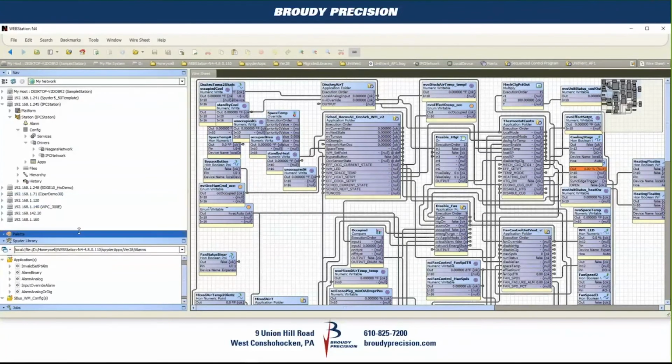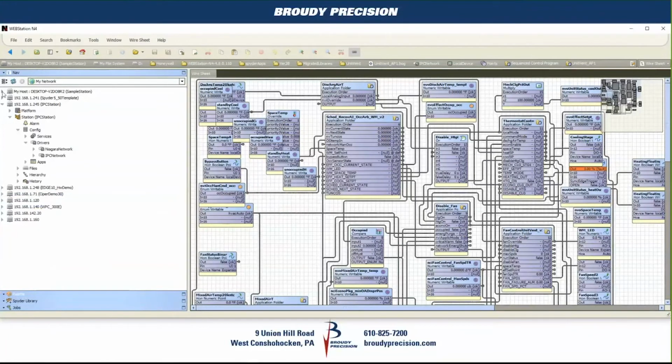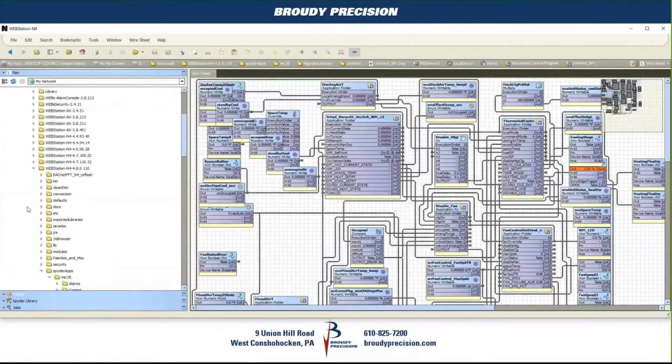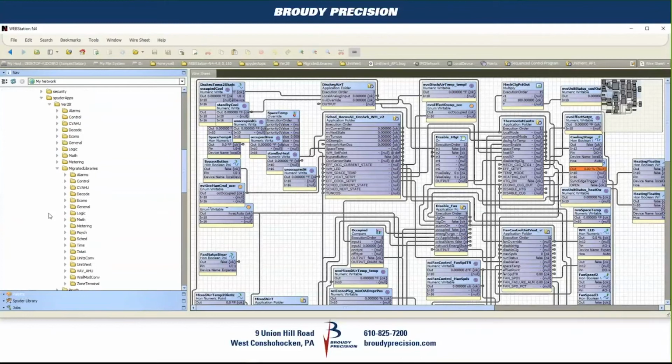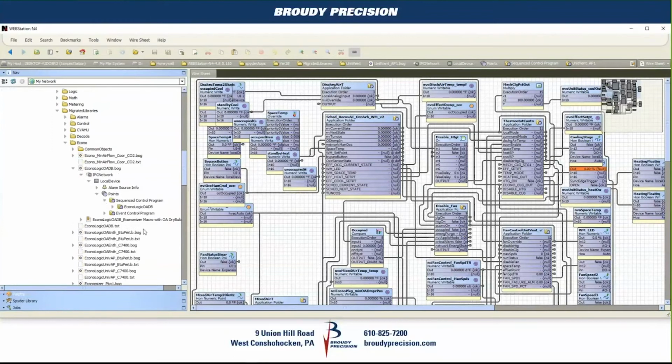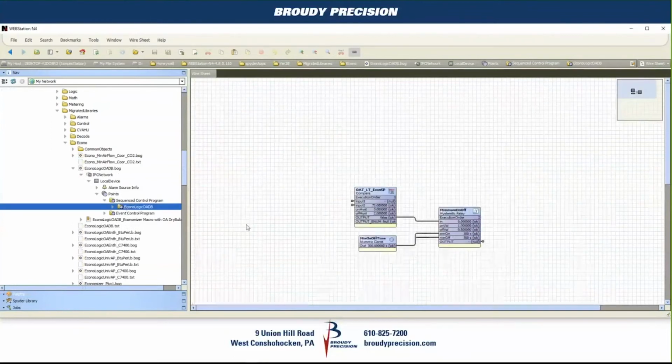But in any case, all those applications, as I mentioned, if we go back up here, they're all located here. So if you like using certain pieces of their logic, like you like their economizer logic with outside air dry bulb, you don't need to go in through the library to get to it. You could just copy that piece there and you have the logic pulled in with it.